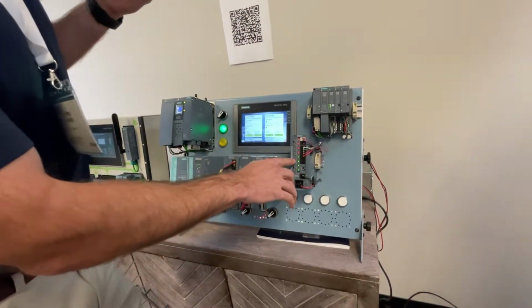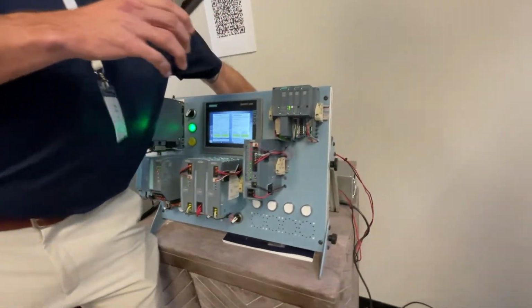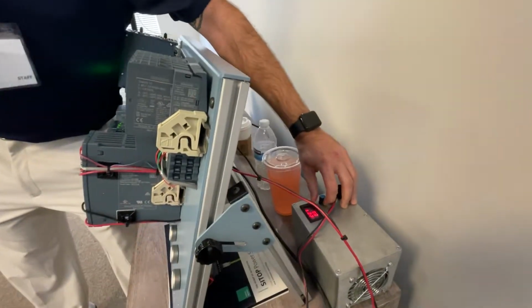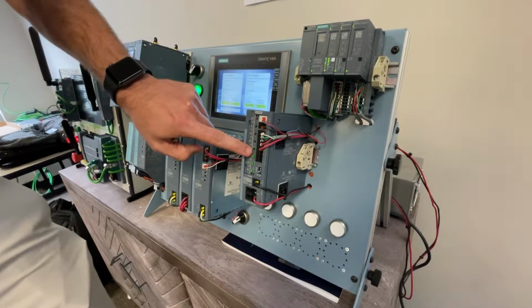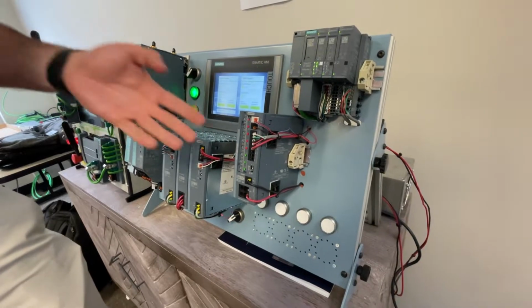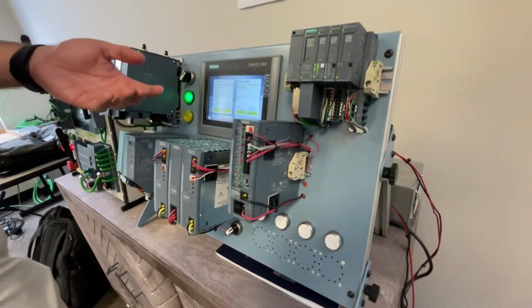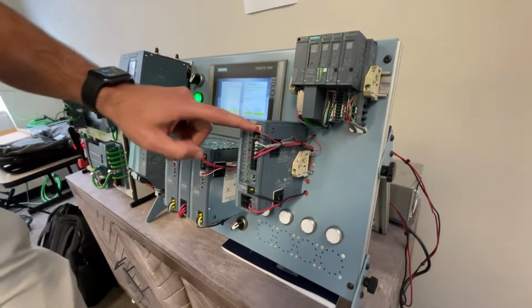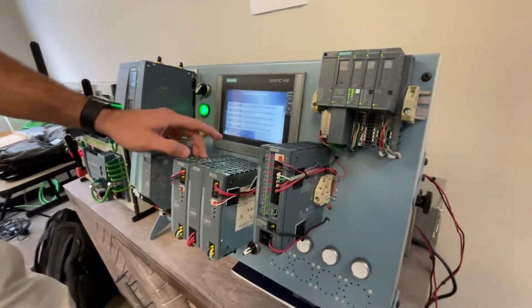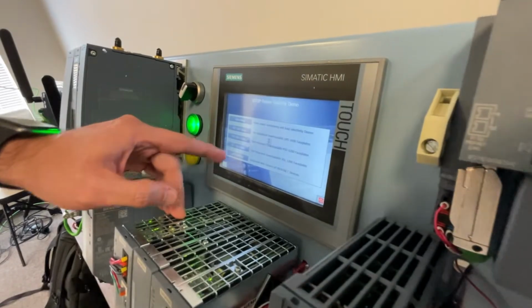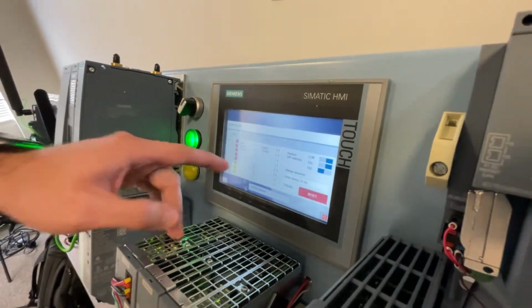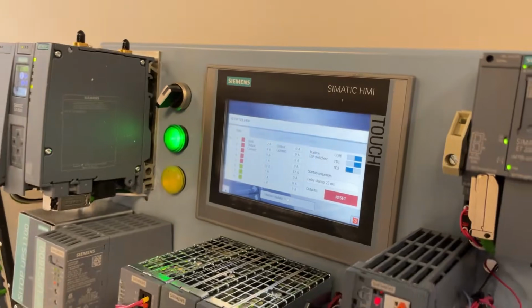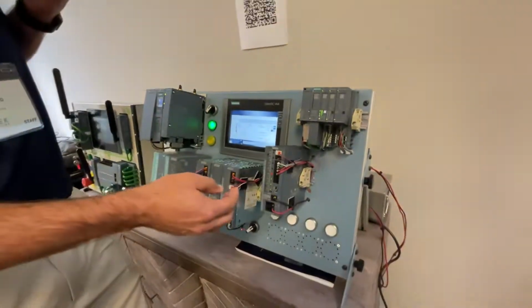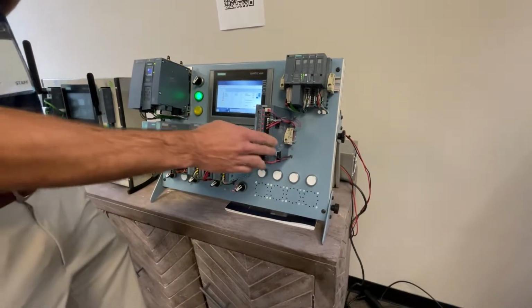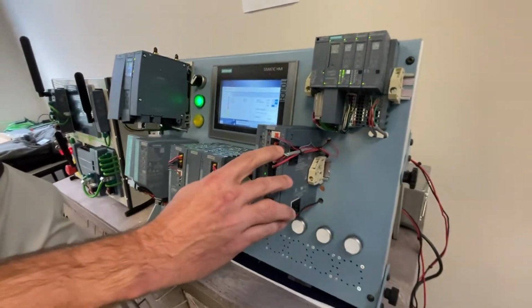So that's the short circuit test, and I also have right behind a load box. I'm going to crank this up to go above the threshold limit for output number 5. You see it's starting to blink to let you know you're going to overload, and then it turns off. So it's very smart, and also just like the power supply, it has that diagnostics interface port. There's also a function block and faceplate available, so you can actually see the status of the selectivity module as well. And a really good feature of this module that a lot of customers like is the remote reset functionality. There's an RST right there, which stands for reset.